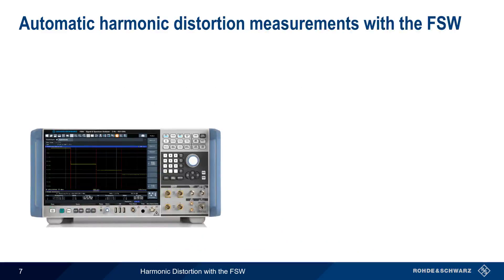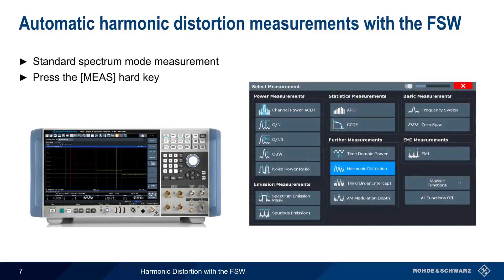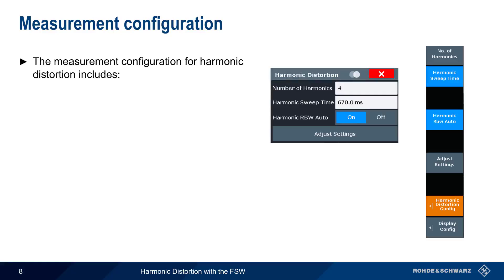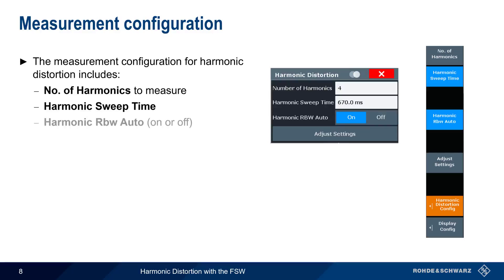On the FSW, harmonic distortion is one of the standard spectrum mode measurements. Just press the Measure hard key and select harmonic distortion from the list of available measurement types. The parameters needed for harmonic distortion measurement include the number of harmonics to measure, the sweep time or measurement time, and whether or not the resolution bandwidth should be automatically adjusted. We'll come back to these last two parameters momentarily.